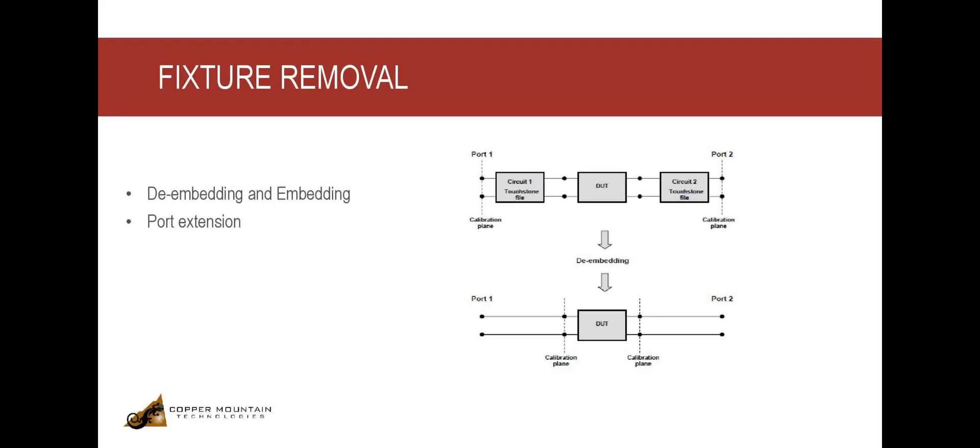If the measurement plane is different from the calibration plane, de-embedding, embedding, and port extensions can help compensate for the loss caused by the additional fixture. These functions are usually a built-in feature in most VNA software.